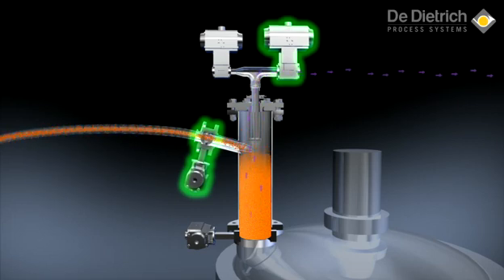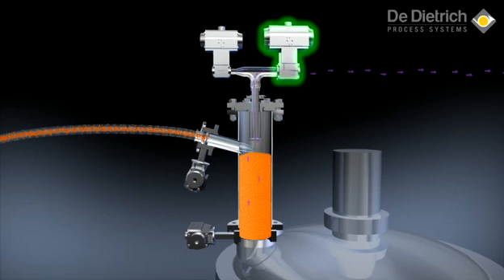When the preset transfer time has elapsed, the powder inlet valve closes. A brief delay allows residual air to be evacuated, then the vacuum isolation valve closes.